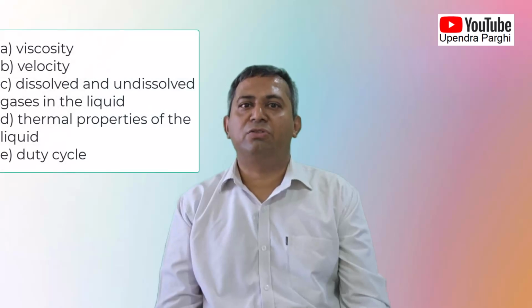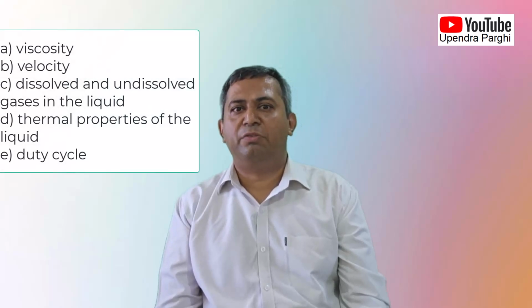One other important thing which I wanted to mention is that there are other scale factors which are not considered. However, they do affect the intensity of the cavitation. Those are viscosity, velocity, dissolved and undissolved gases in the liquid, thermal property of the liquid and duty cycle. Do note that the test is done on water, and hence if the media is different, the properties will come into effect to give you the exact value.